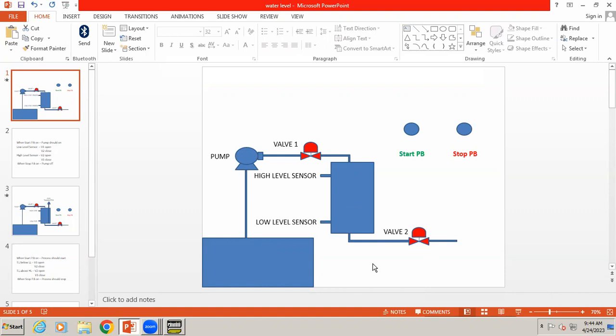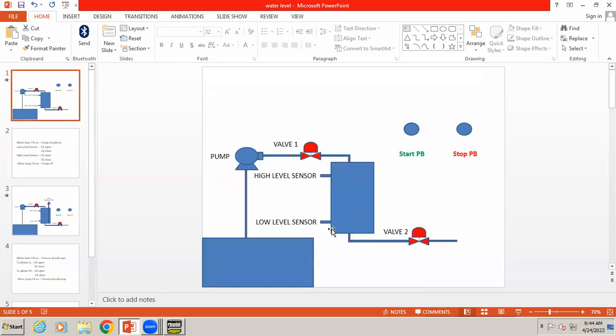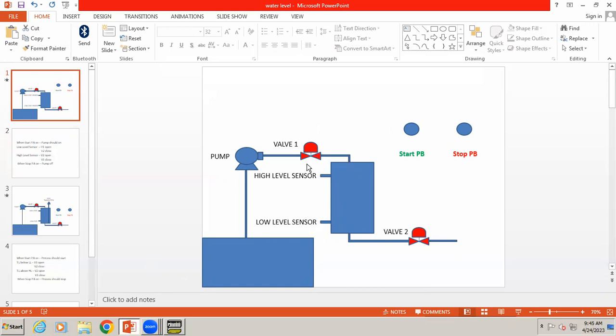The process should keep on repeating. When we press the start push button, pump should turn on; low level sensor is ON, so valve one opens and valve two should be in closed state, so the tank level increases. But remember: once the tank level rises above the low level sensor, the sensor will immediately turn OFF. If the sensor turns off, the valve would close immediately. However, the condition requires valve one to close only when it reaches the high level sensor. So even when the sensor is OFF, the valve should remain open — we have to use the latching concept in this program.